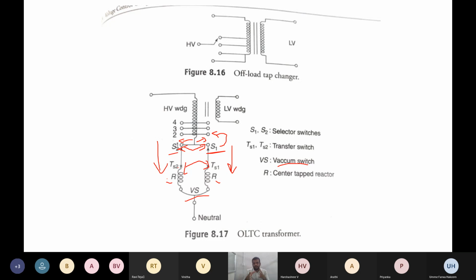If you try to change the position with the transfer switch on, on load, at that time we can witness a huge amount of lightning or sparks. That's why open the transfer switches, change the position, and close the transfer switches. Similarly here also, shift S2 from position 1 to position 2. Before that TS2 should be open, change the position of S2, and close TS2. Like this the operation takes place in tap changing transformers.